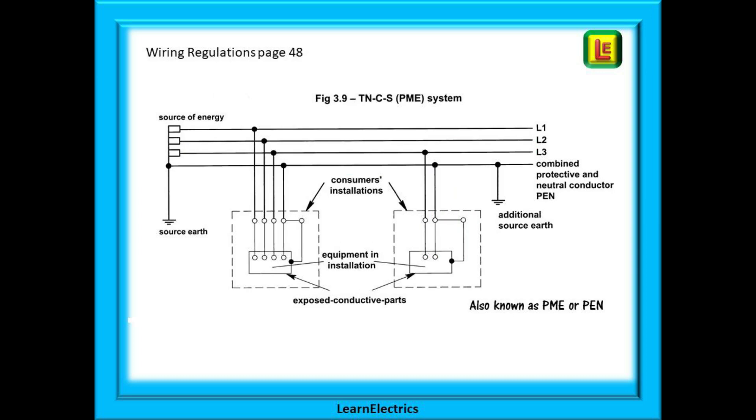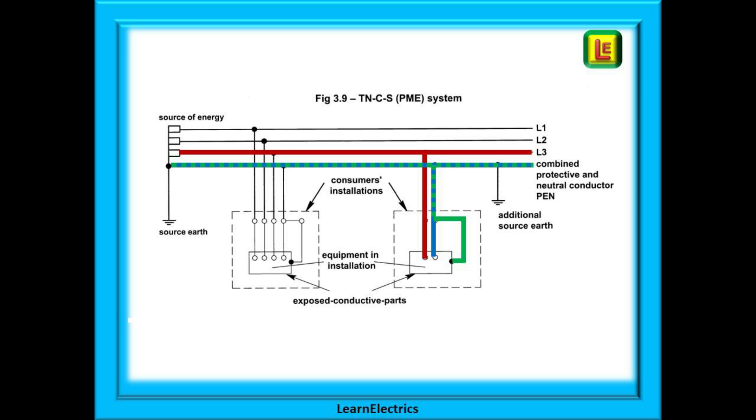Now we can look at a TNCS system. If you look at the title to this schematic you will see that the TNCS system can also be called a PME system. The phase conductor is as before. But now the earth and the neutral leave the supply transformer as one conductor. They are combined. Shown here as a dotted blue and green line. Look at the note on the right in the red box. This combined conductor can also be called a PEN conductor. And then at the intake position the earth and the neutral are separated. This is a TNCS system. Also called a PEN or a PME system.